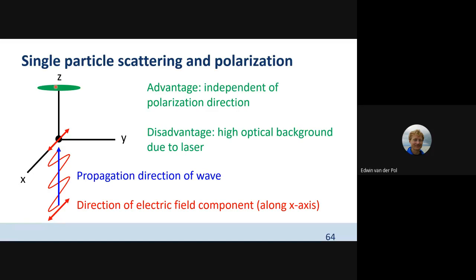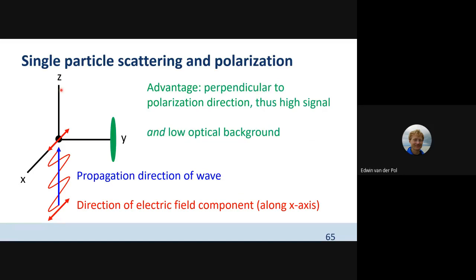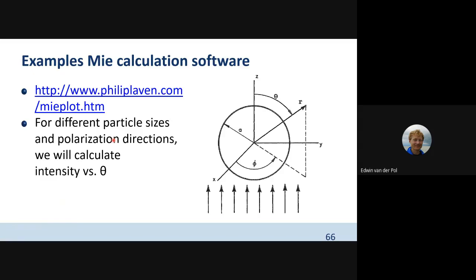For the lens placed at the z-axis in the forward scatter direction, it wouldn't matter how you polarize the light — you'd always pick up scattered light with this lens. But it has one important disadvantage: if you want to collect forward scattered light, you also have to deal with high optical background because the laser propagates in the same direction as the lens, making it very difficult to differentiate particle scatter from the much stronger laser light.